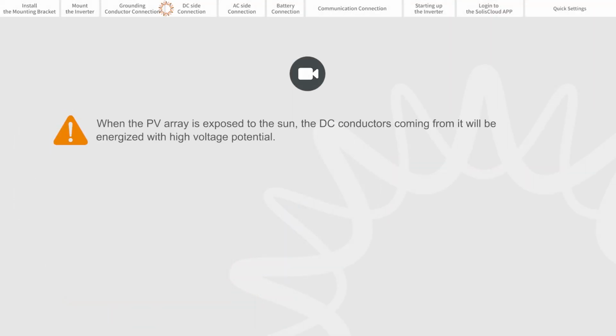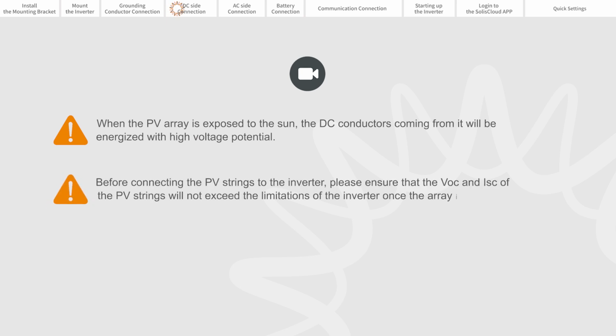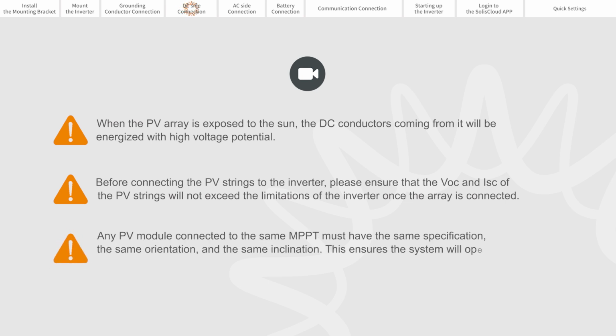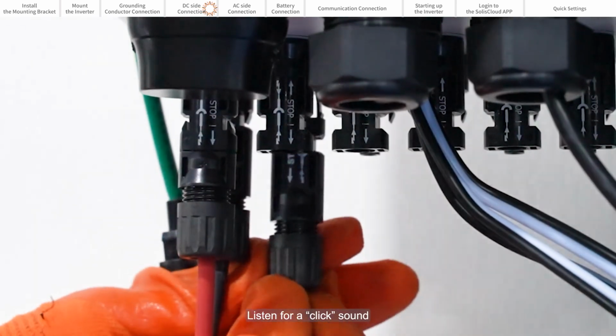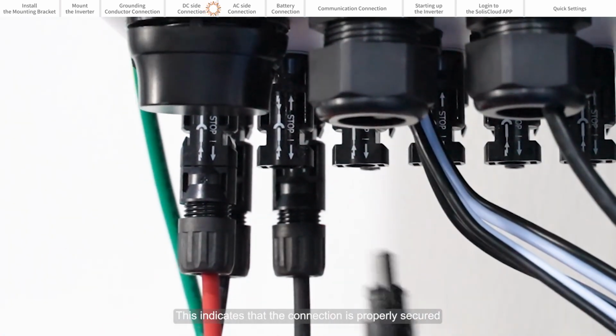DC side connection. When the PV array is exposed to the sun, the DC conductors coming from it will be energized with high voltage electricity. Before connecting the PV strings to the inverter, please ensure that the VOC and ISC of the PV strings will not exceed the limitations of the inverter once the array is connected. Any PV module connected to the same MPPT must have the same specification, the same orientation, and the same inclination. This ensures the system will operate at maximum efficiency. Listen for a click sound. This indicates that the connection is properly secured.